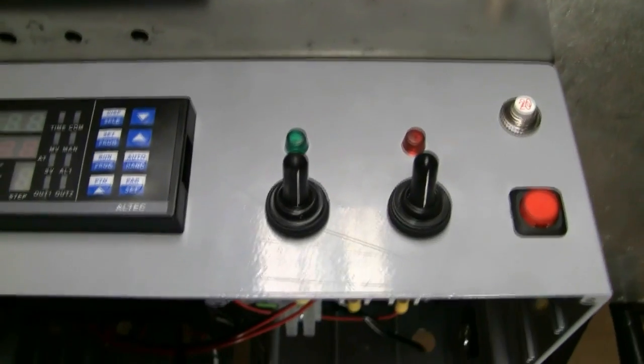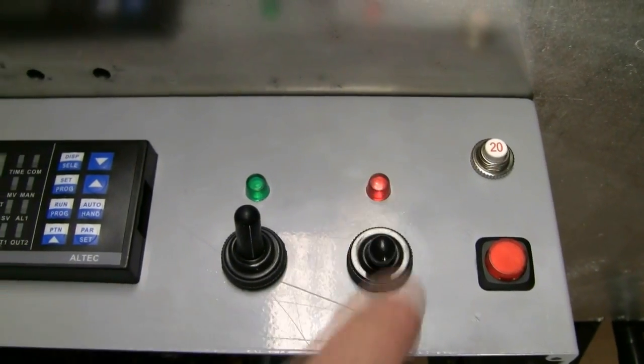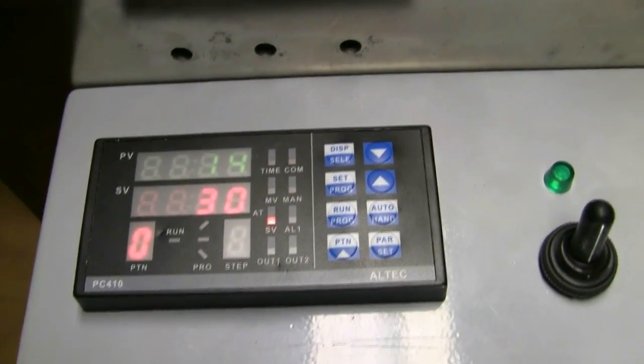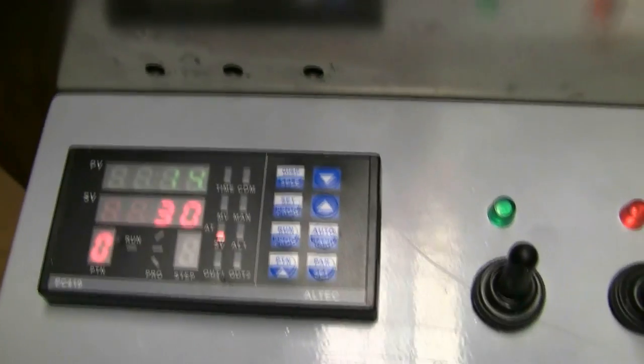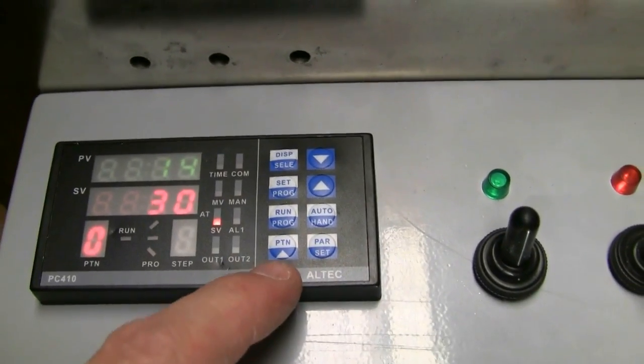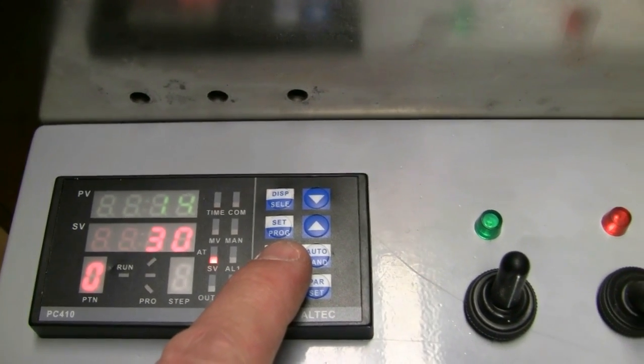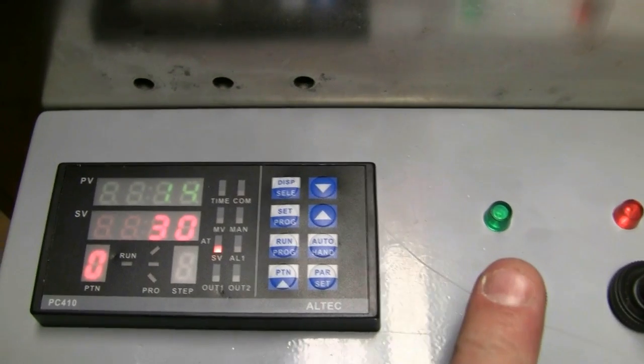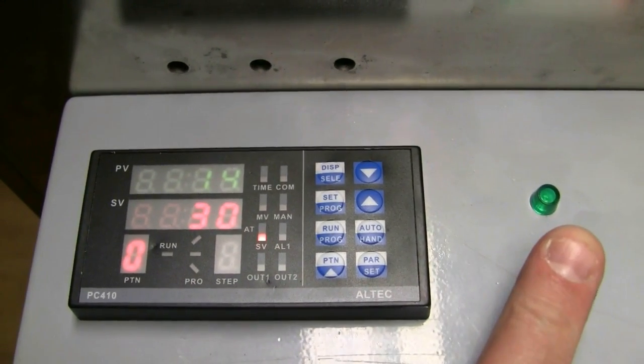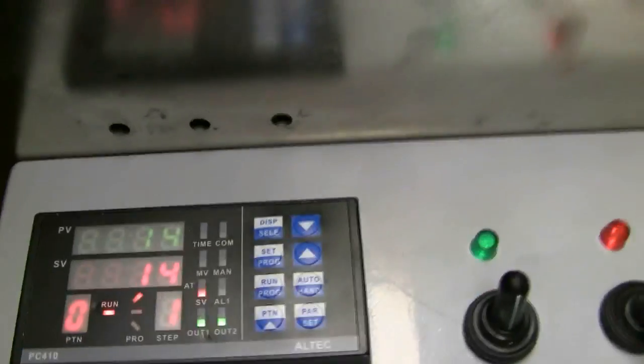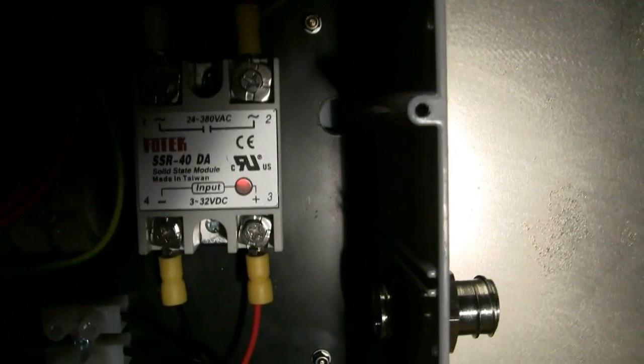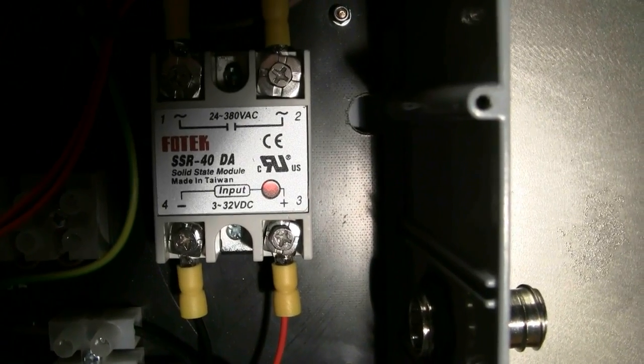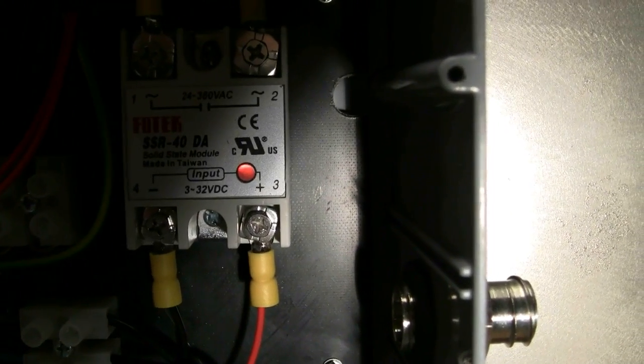Basically what happens is, if we switch it on, the PID controller comes up. There isn't an awful lot to see because there's no heating element. But if I press run on here, or I can switch this into a hold mode, and if you put it back into run mode, the controller comes on and you can see the red light on the solid state relay. The solid state relay is now being successfully switched by the PID controller.